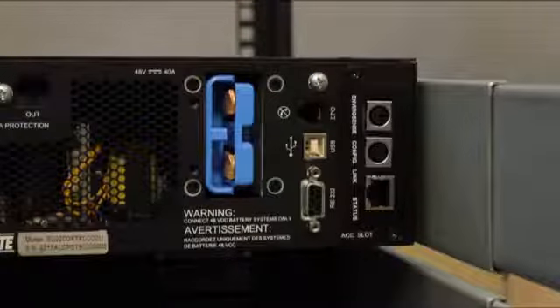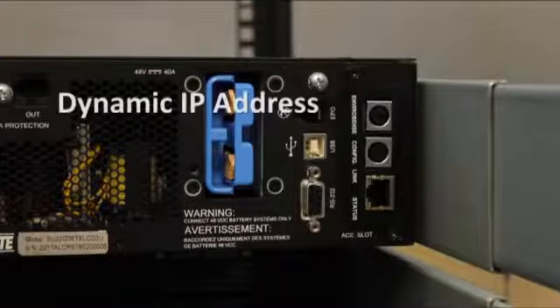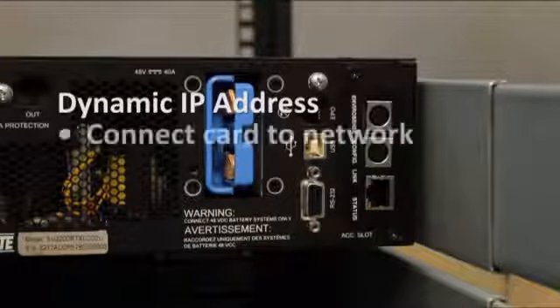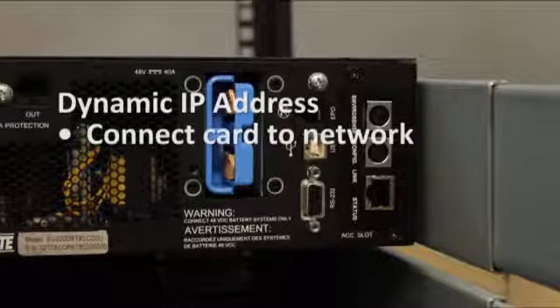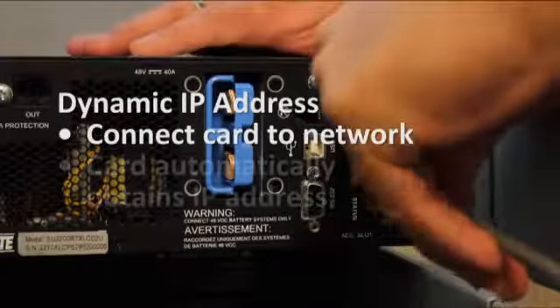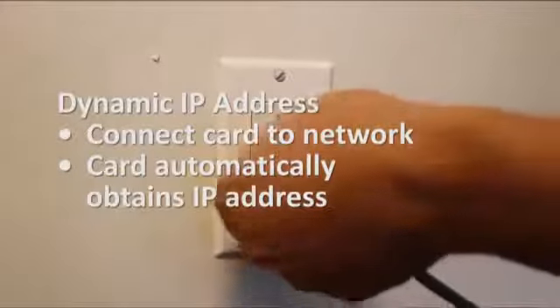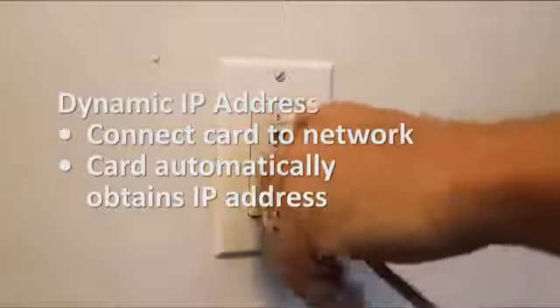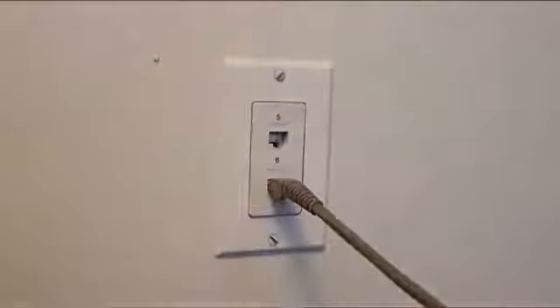Check with the network administrator whether the SNMP web card will use a dynamic or static IP address. If it will use a dynamic IP address, connect a network cable from the Ethernet port on the card to a network jack. The card will automatically attempt to obtain an IP address via the network's DHCP server. This may take several minutes depending on your network.